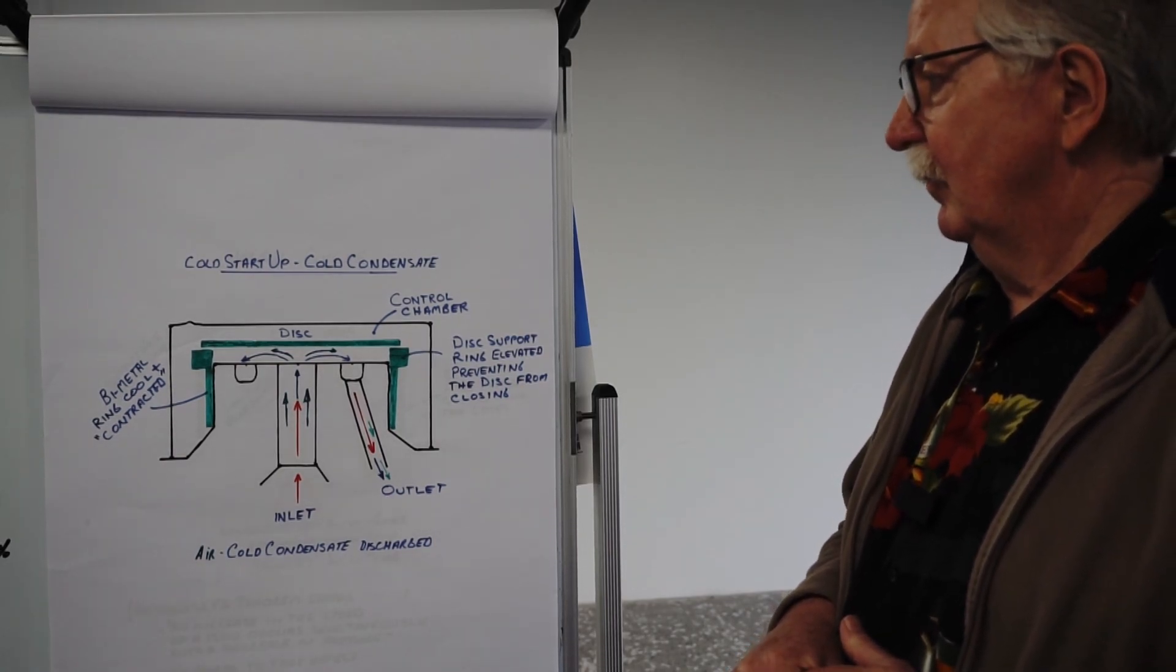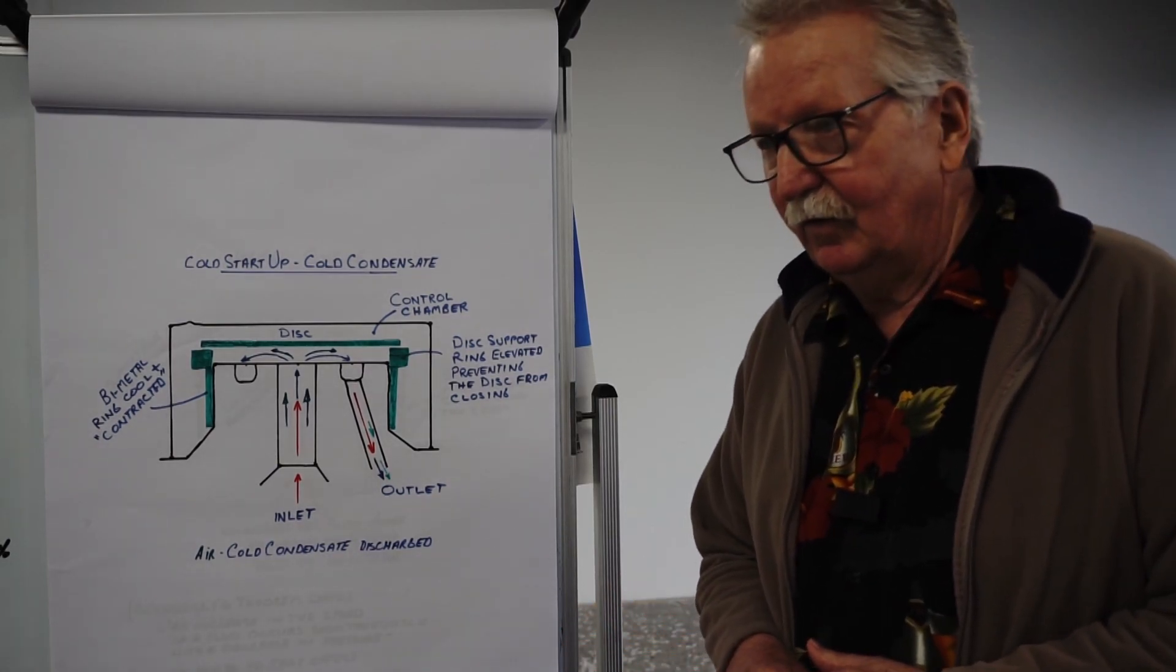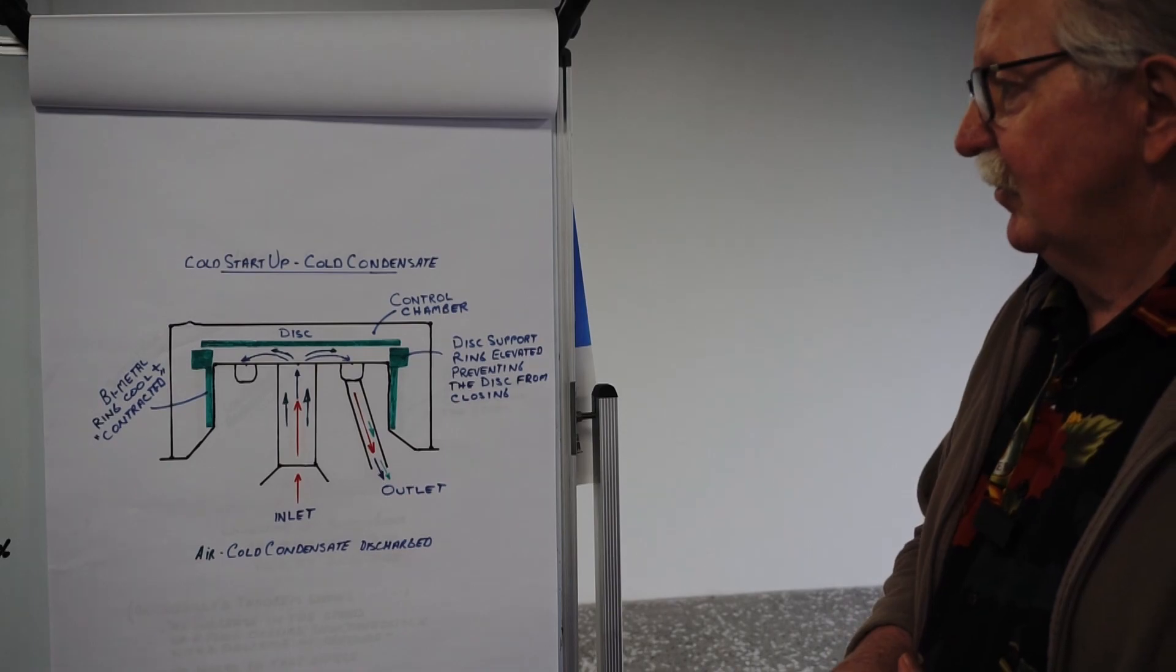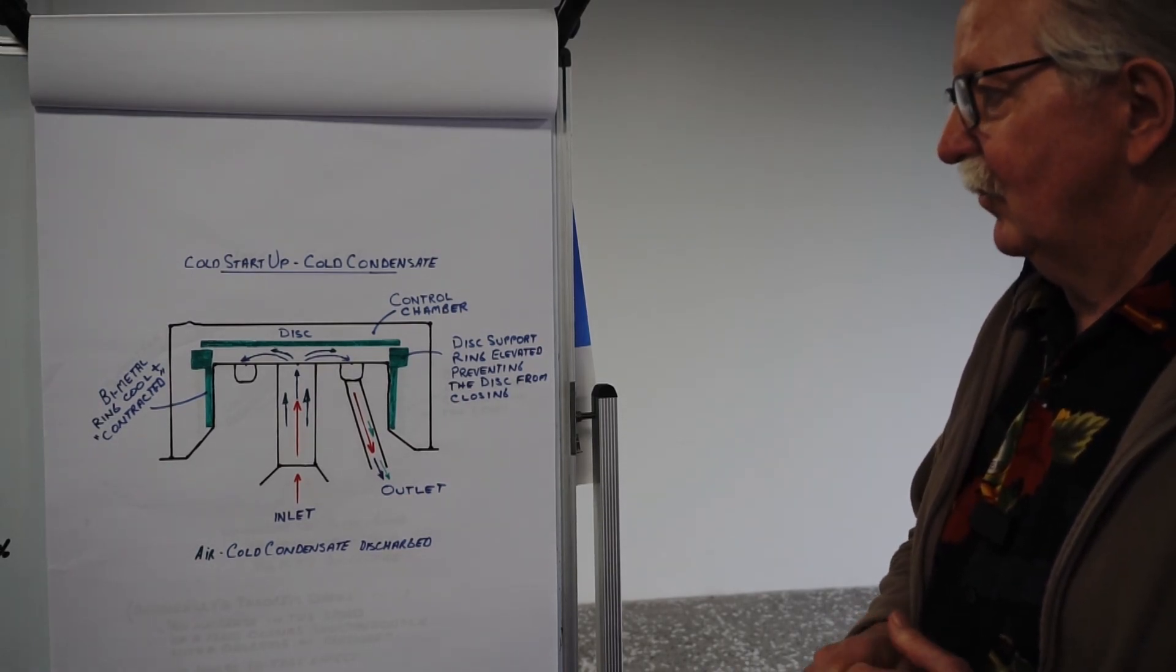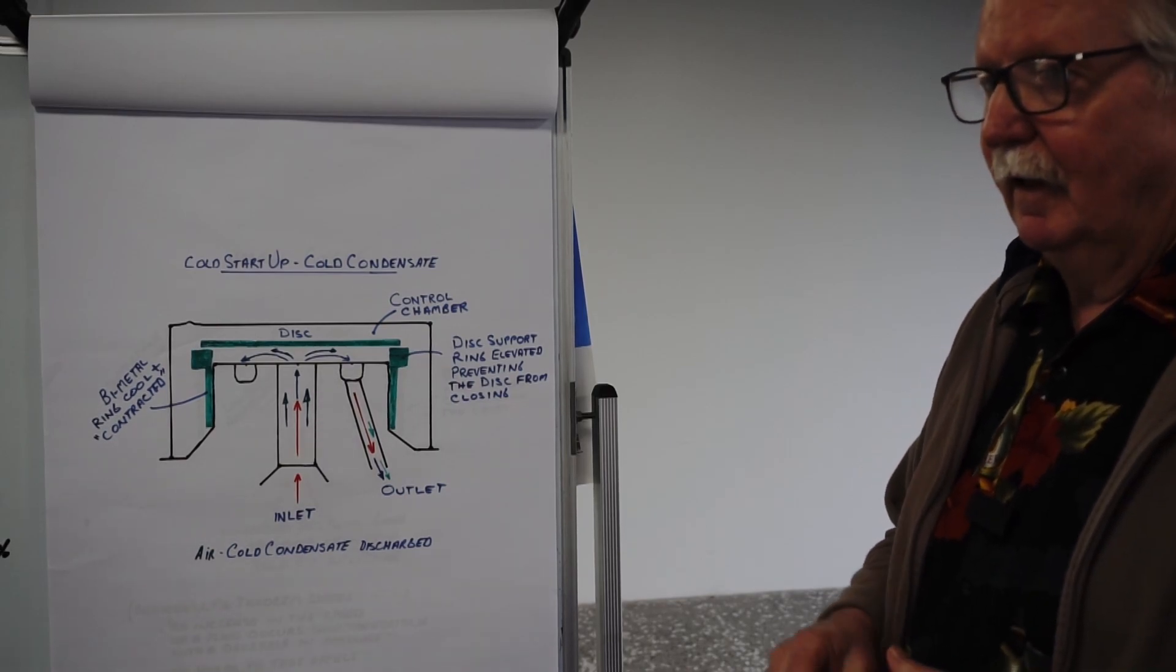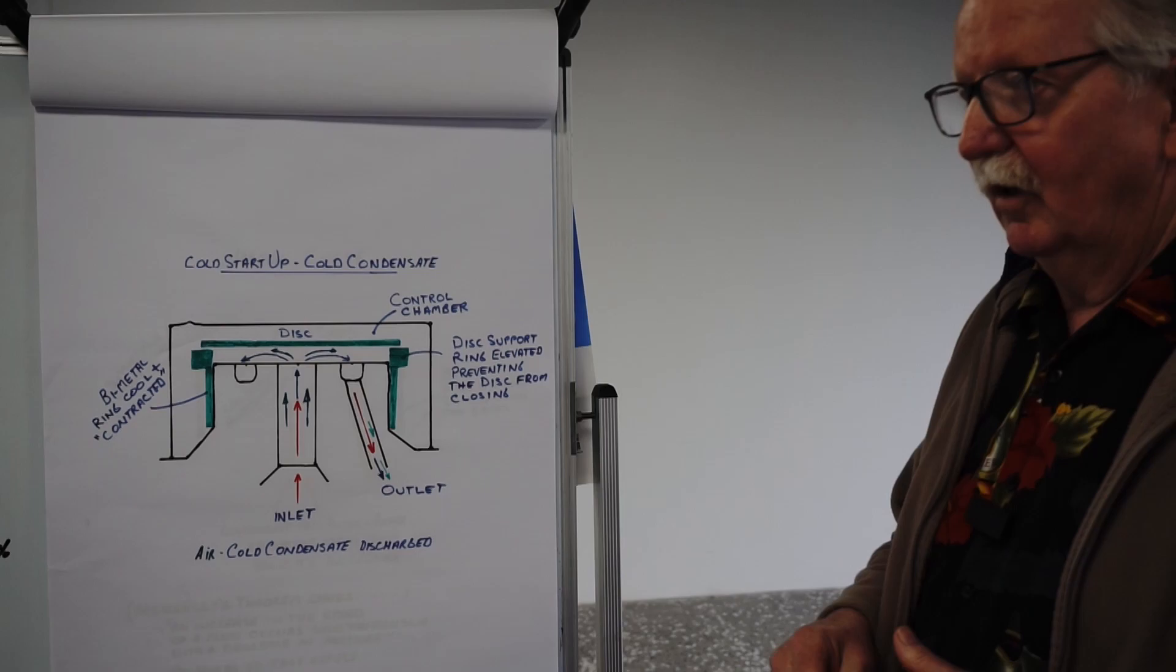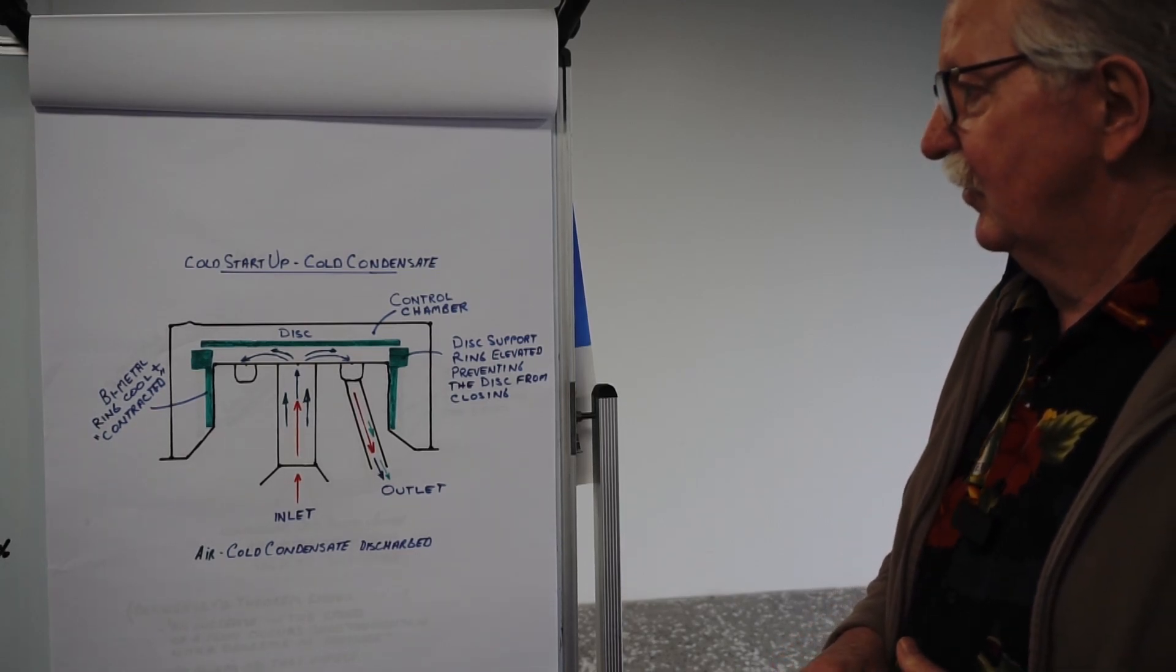They're suitable for various pressures but do have limitations on minimum pressures and usually are not suitable for operation below about 80 kPa. They need a certain amount of pressure to create the thermodynamic process on the disc.